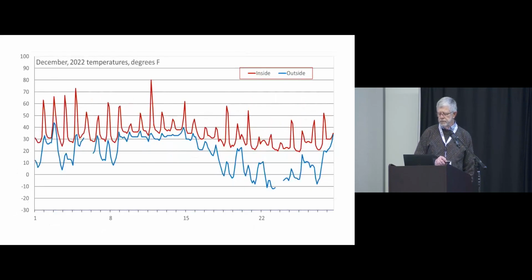December got to be a little more challenging, but so far we're keeping above our 20-degree threshold. This is not operating continuously—it's on a thermostat, so it comes and goes as needed. If you had it run continuously you could probably keep it warmer, but then you're wasting heat. There's only so much stored in the ground. If you use it when you don't really need it, you won't have it for when you do need it. So it's important to have it on a thermostat so you don't squander it.